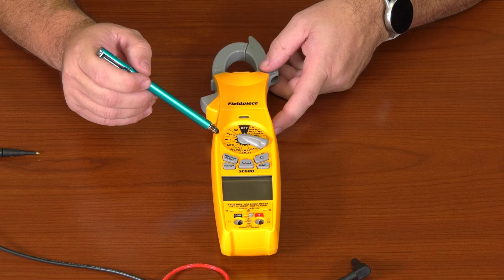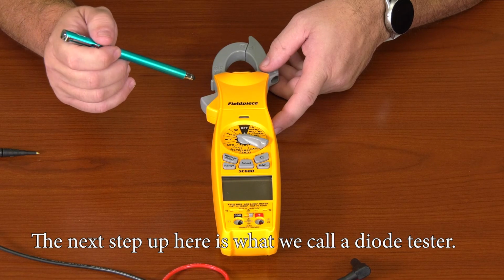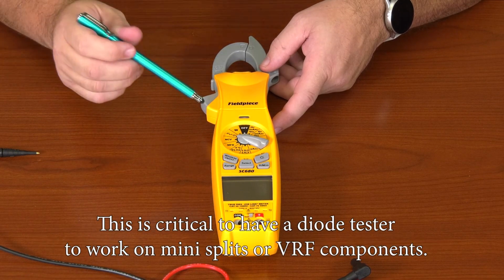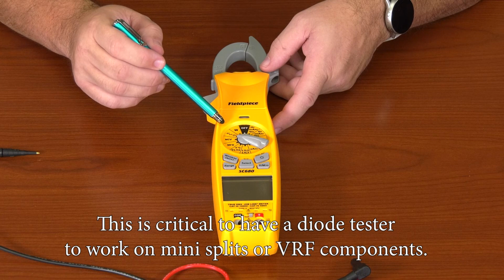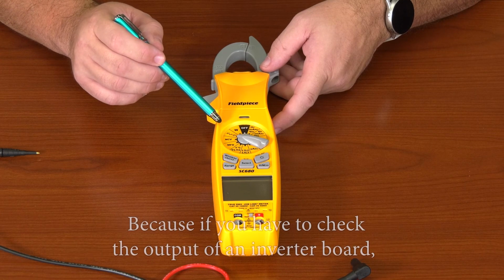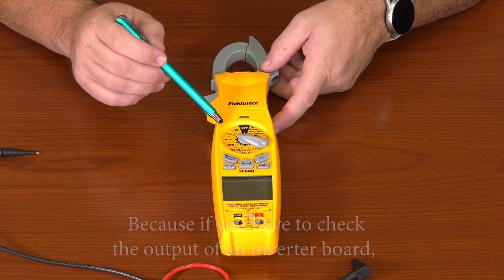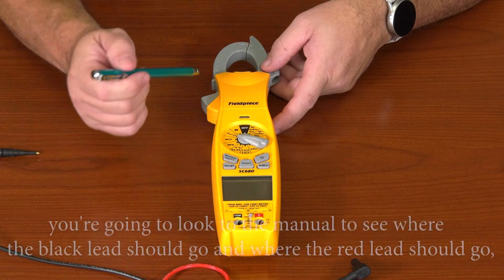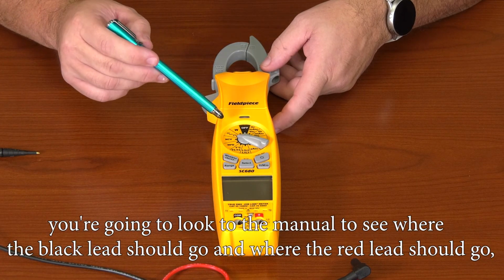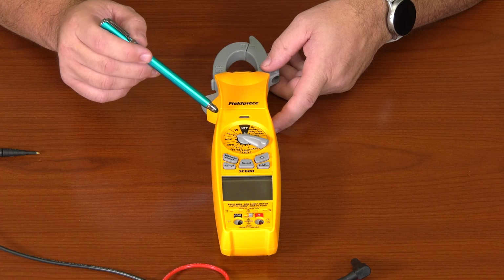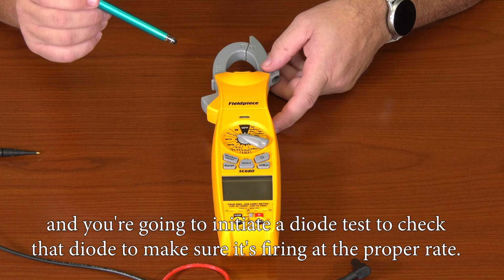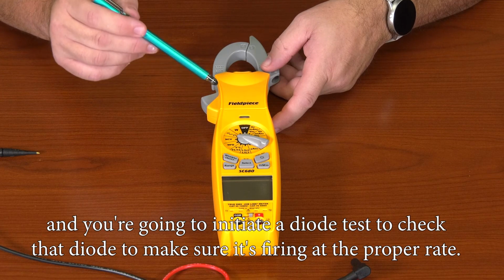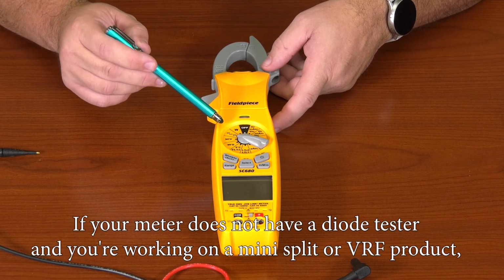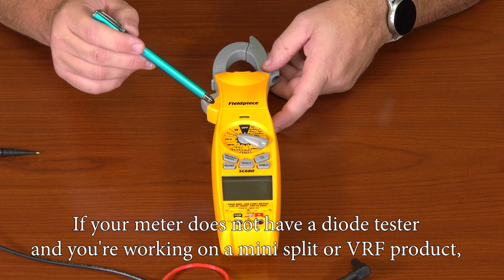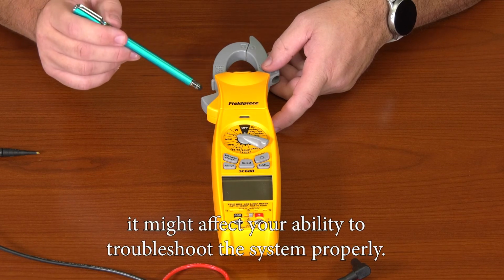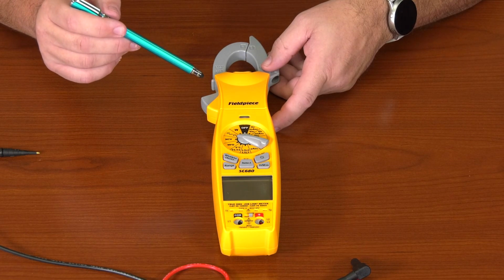The next step up here is what we call a diode tester. This is critical to have a diode tester to work on mini splits or VRF components. Because if you have to check the output of an inverter board, you're going to plug your leads in, you're going to look to the manual to see where the black lead should go and where the red lead should go, and you're going to initiate a diode test to check that diode to make sure it's firing at the proper rate. If your meter does not have a diode tester and you're working on a mini split or VRF product, it might affect your ability to troubleshoot the system properly.